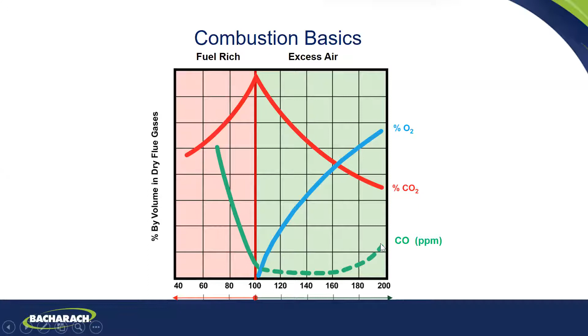But it gets a lot lower as you add in the oxygen. And then as you add too much, you get way out here. I mean, you really shouldn't be there because you'd have low efficiency, but if you add too much oxygen, you're going to dilute the sample and you're going to have incomplete combustion again and start making CO. So we really want to be in this area here called our sweet spot.